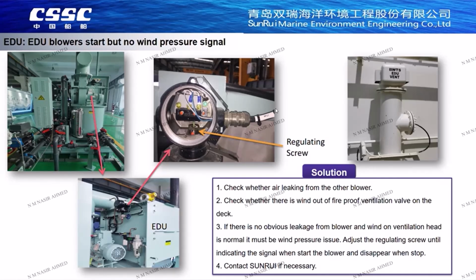After opening the cover, you can see a big nut. The sensitivity of the nut may be changed due to the vibration on board or other reasons. The nut can be adjusted up and down to achieve the wind pressure signal on when the blower starts and the wind pressure signal off when the blower stops.